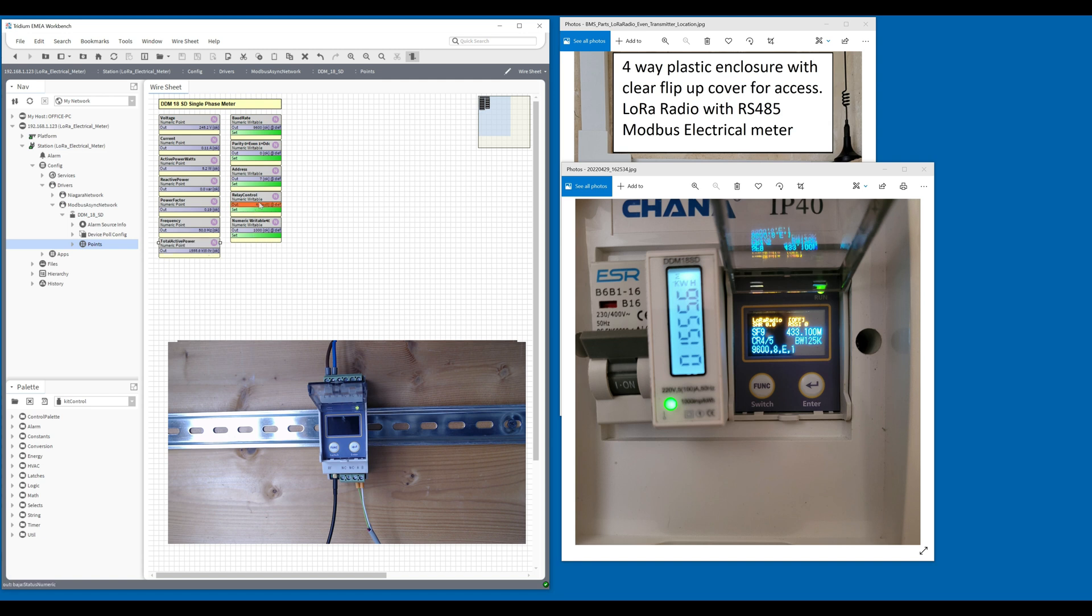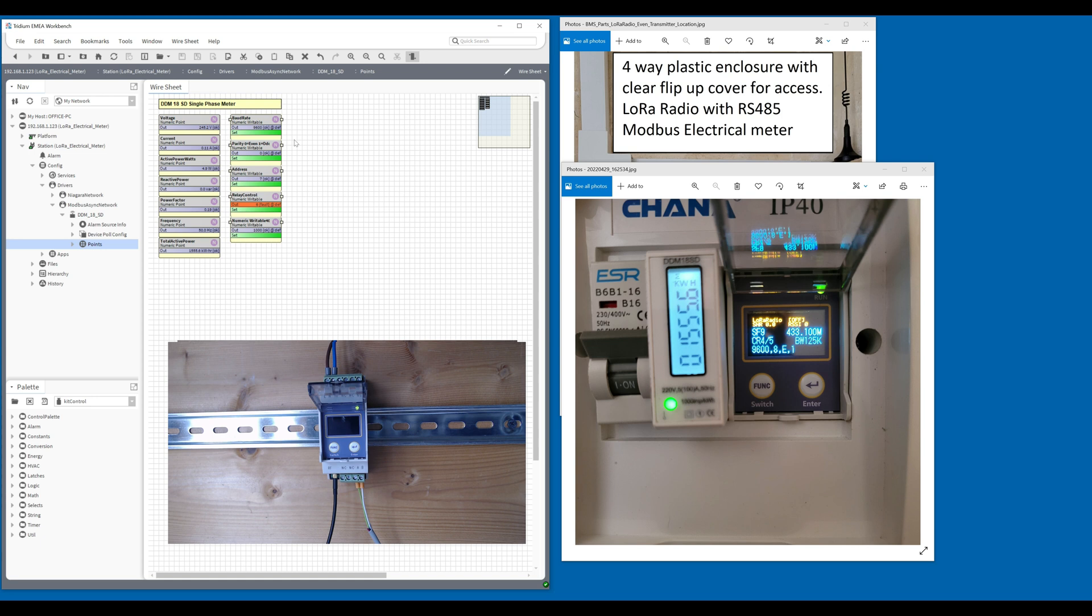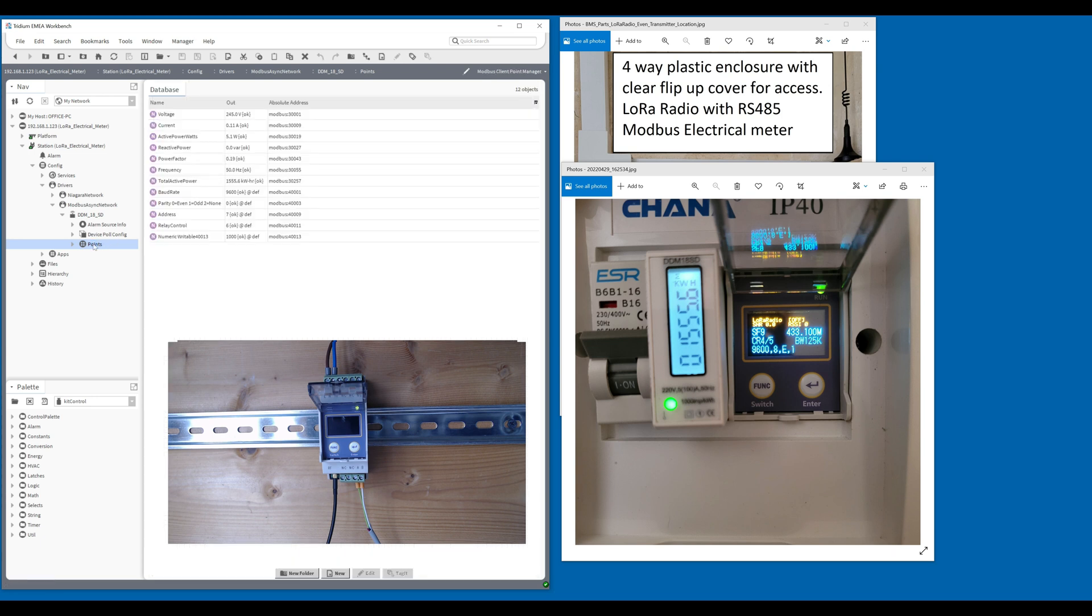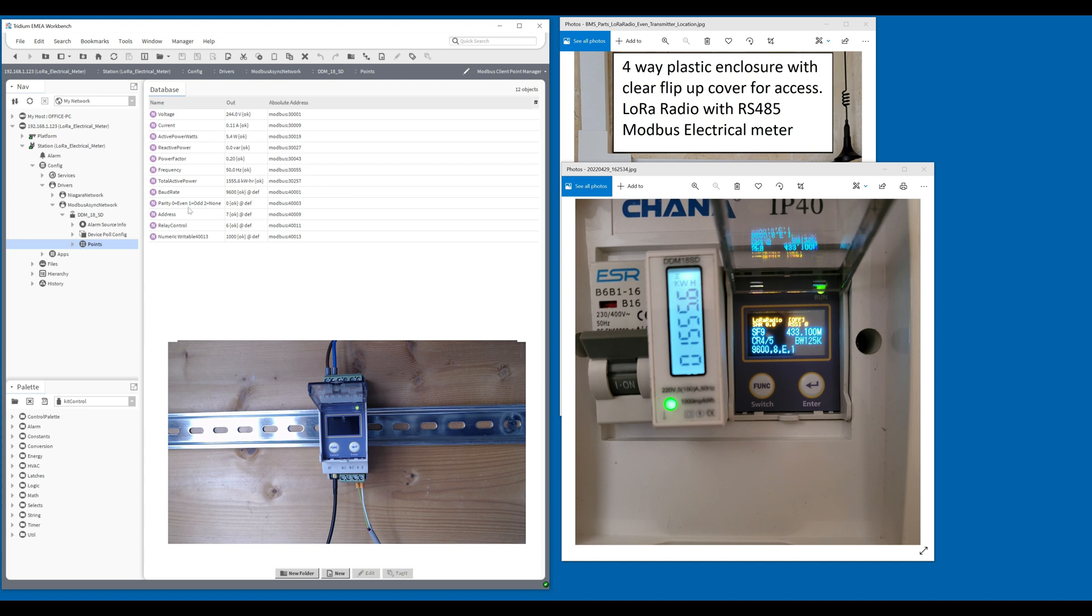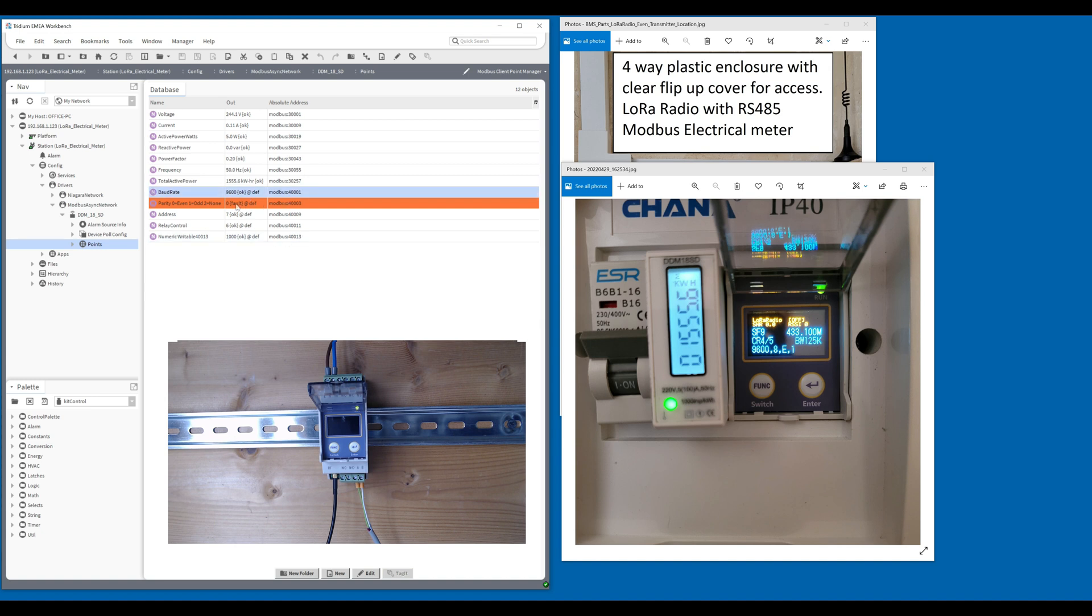It's communicating. These boxes here, it's just setting it all up, and they're not required, but I put them in. If we look at the Modbus codes for this particular meter, they're here, 3001 for the read registers, and then 4000 for the setup of the system, the baud rate, the parity, the address. Not really interested in these figures, but they're there anyway. It's gone into fault there, but it will clear itself on the next poll.